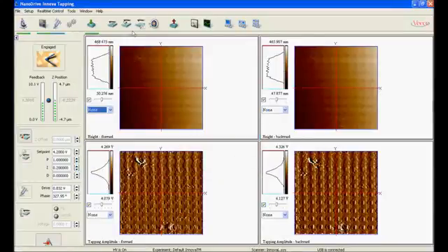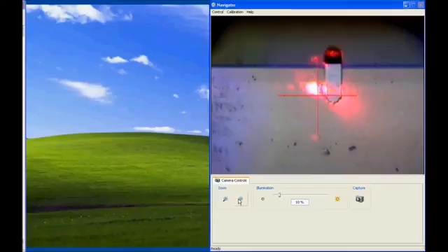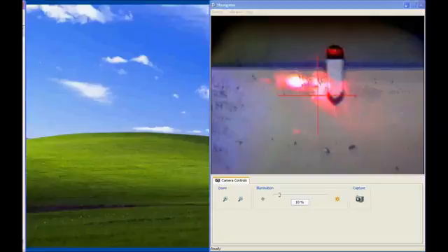I click the withdraw icon to lift the tip from the surface. Just to be safe, I typically do this 2 or 3 times. Note the info window in the upper left now reads Withdrawn, and the bar beneath the Engage button is red. In the microscope, we can see how high each click of the withdraw button lifts the cantilever.